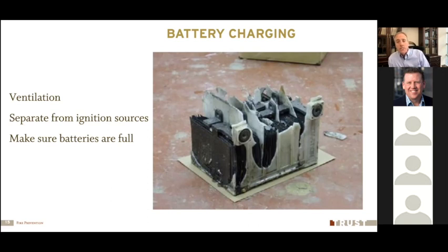A lot of batteries today aren't wet cell batteries. We see batteries that have gel inside of them instead of water, or we have lithium ion batteries. But we do have a lot of battery charging. A lot of our equipment now is battery operated, and so we're recharging the batteries for this portable equipment. And those battery charging operations sometimes will get very hot. And often you can have a fault or a failure in that battery charger that can result in a fire.